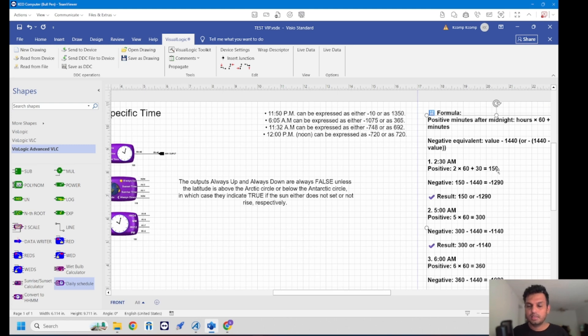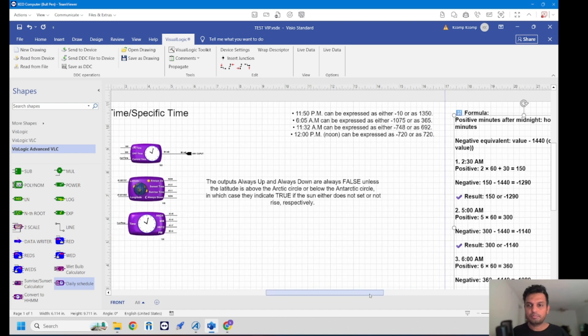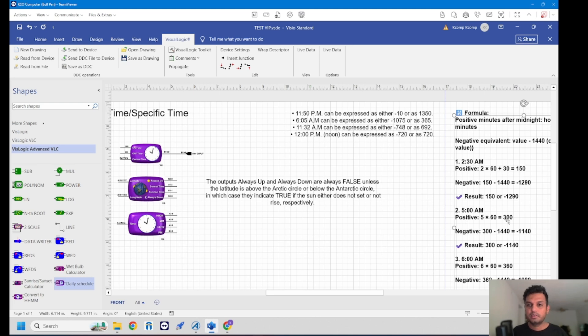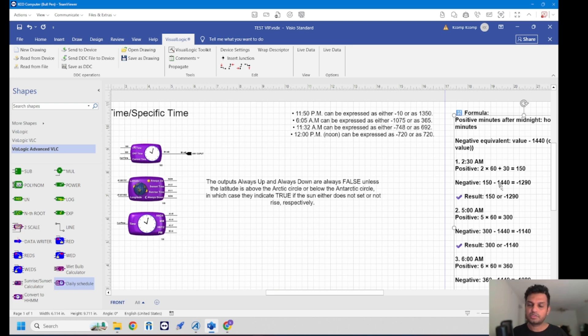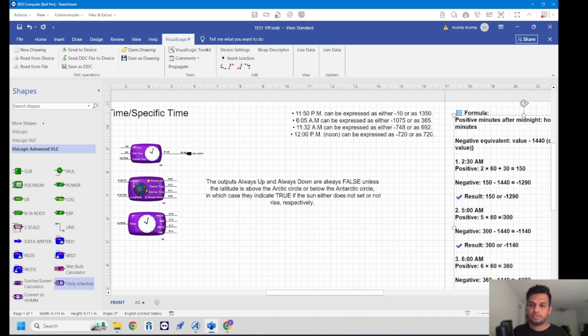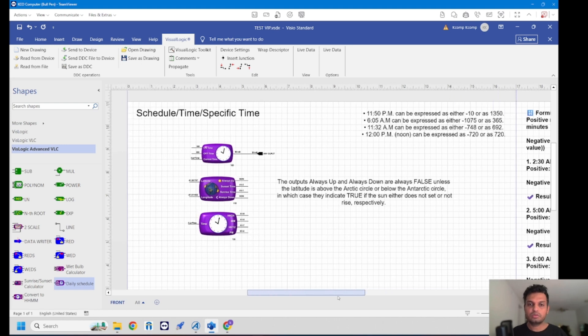Let's say I want to turn on or off the pump at a particular time. I'm going to use the conversion. I need to turn on a pump around 2:30 AM which gives me a converted value of 150. Then I want to turn off a pump around 5 AM in the morning which gives me a positive value of 300. Can I use a negative value? Of course yes. You can use the negative value like what is converted here. Basically you're going to use the whole number of positive output and then use the constant value which was 1440 to convert that to a required timestamp. I'm going to use the positive end of it for now, so 150 and then 300.